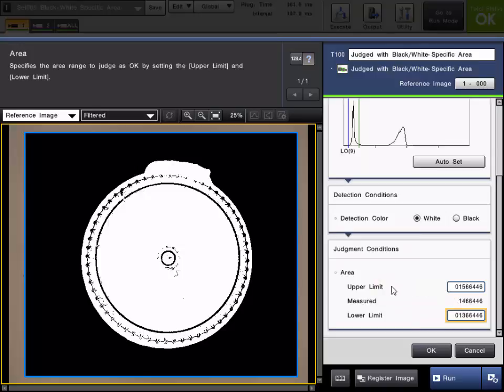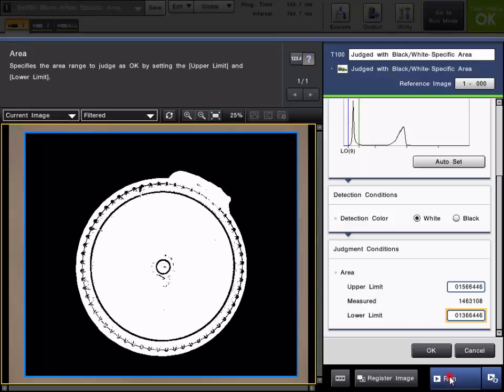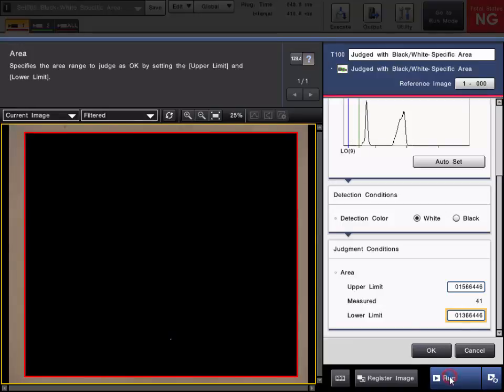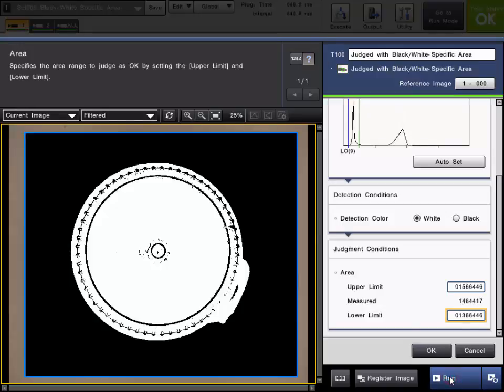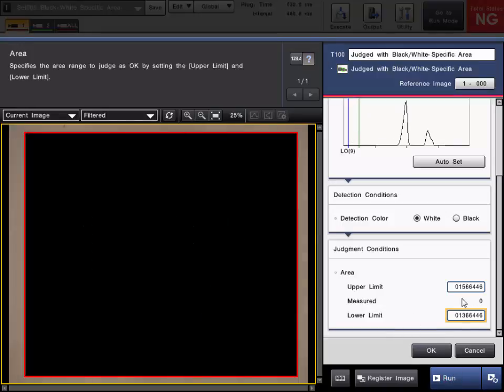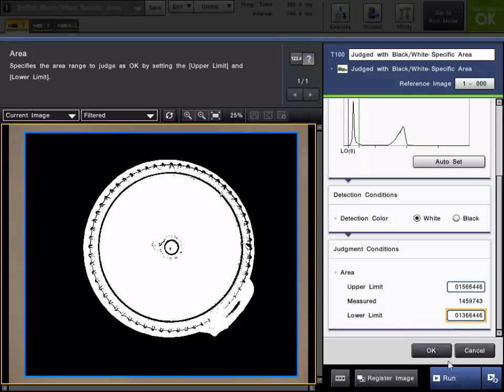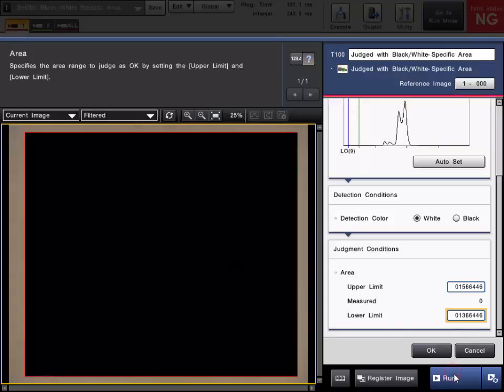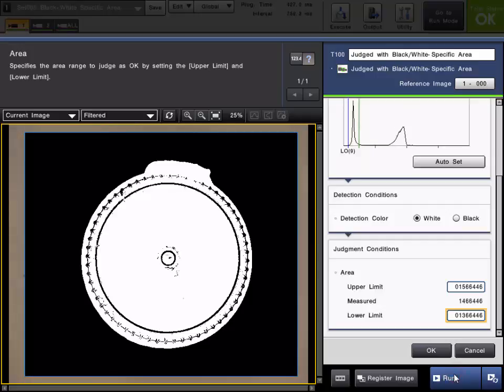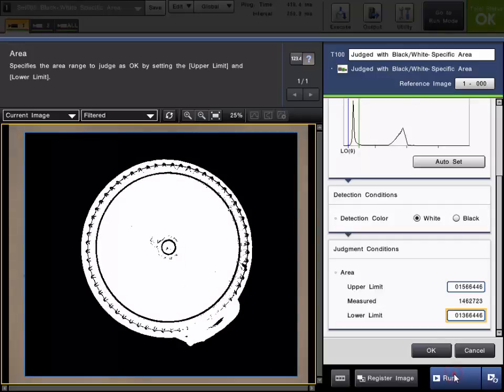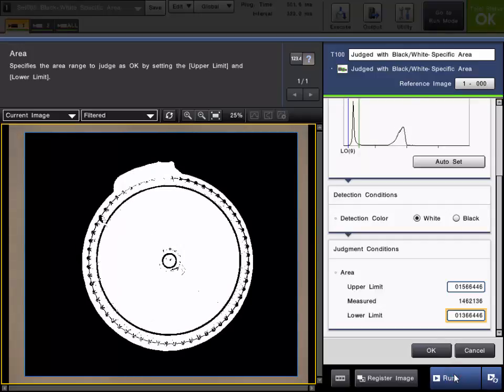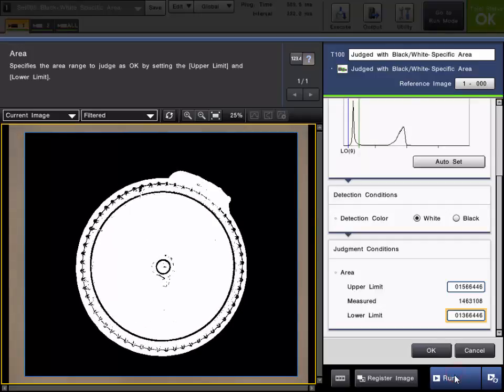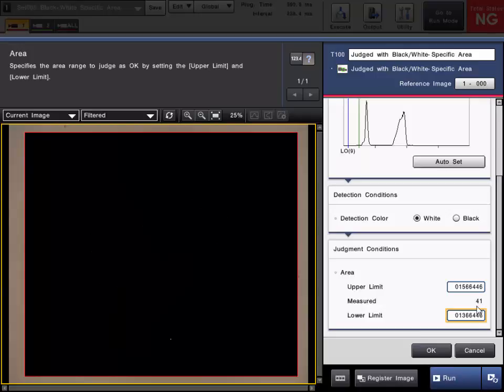Once you set your upper and lower judgment limit, you can actually run some parts if you'd like to confirm the operation. As long as the measured value falls within the upper limit and lower limit, the tool will pass OK. If it falls outside the range, you can see the tool will fail. So here is a low count and you can see the tool fail.